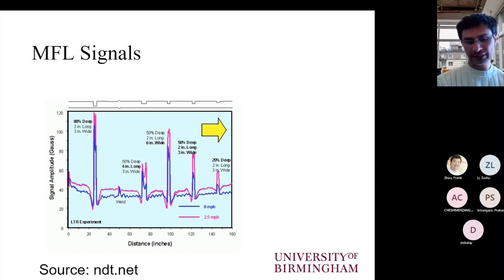But also we are beginning to distort the magnetic field. So some of the flux is lagging behind, distorted from where the sensors are, and that results again in somewhat lower signal being detected by the sensing instruments of the magnetic flux leakage device.